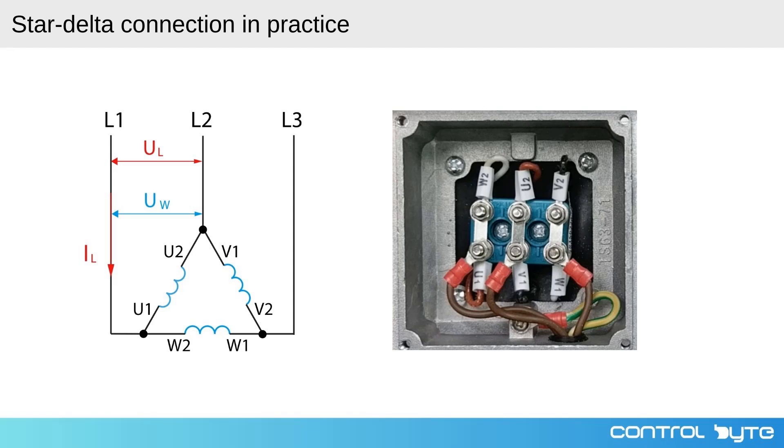The image on the right shows the actual motor terminal box where the windings are connected in a delta configuration. The connections in the terminal box correspond to the delta connection shown in the schematic. You can see that U1 is connected to W2, V1 is connected to U2, and W1 is connected to V2. These connections ensure that each motor winding is exposed to the full line voltage, allowing the motor to operate at its full power capacity.